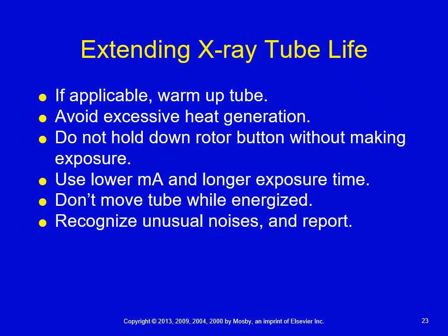So again, tubes do have warm-up procedures. They're more automated now. So basically, if your tube sits idle for a long period of time, or let's say you're in an ortho facility where the machines are turned off at night, when you come in for the morning, someone will be responsible for tube warm up. It used to be a number of exposures that we took at a certain kVp and mAs, but it's more automated now. There may be a selection that says tube warm up, and then it steps you through the process of warming up your tube for the day.